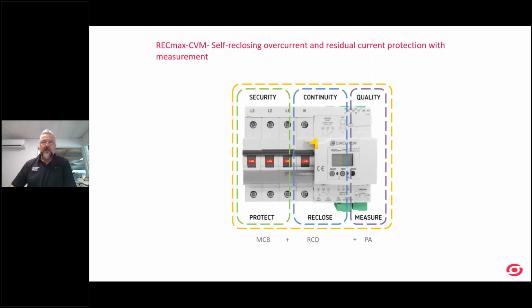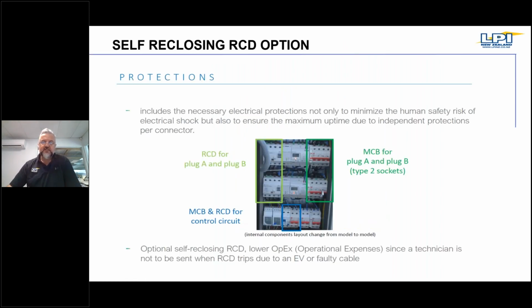is not there. A practical application for something like this could be, for example, let's say on Friday night you have someone coming in with a faulty cable to charge their EV car, or a faulty socket on their car or anything like that, and the RCD trips. Once it trips, of course, you need to get a technician to come and check the operation and test the system and reclose it. With this particular system, which is of course optional, once the faulty unit has been unplugged, the unit itself will do a number of tests, and it will reclose that RCD only in the event that the fault is definitely clear.